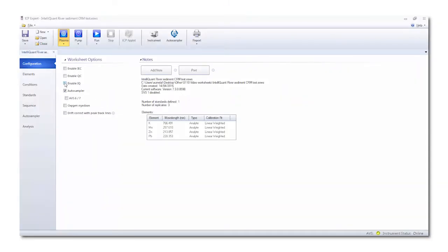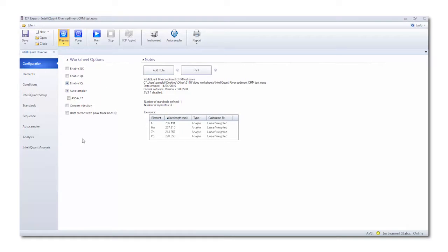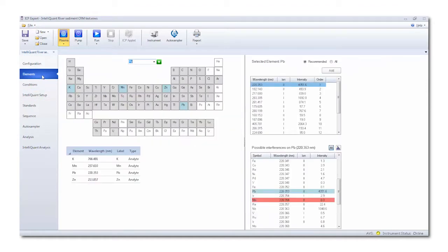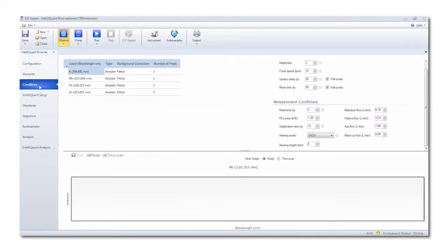IntelliQuant is easy to turn on through the configuration page of ICP Expert software. Activation of IntelliQuant will only add seconds to a typical quantitative worksheet, and for a typical QA/QC laboratory, it provides a lot of additional assurance about what is in the sample. The Elements page allows selection of elements and wavelengths for quantitative analysis, and this is an existing worksheet, so they already exist. Conditions are as per the previous worksheet, so can remain unchanged.